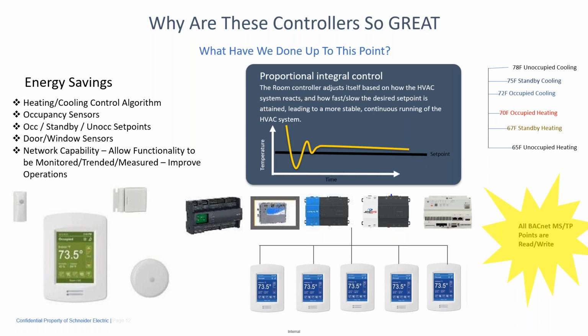points. So you've got the occupied set points, you've got the standby set points, but then you also have the unoccupied set points. If I don't sense motion for a longer period of time, I can go to my unoccupied set points and control to those. So energy savings is built in. You can also add door or window sensors, right? So either that can be hardwired to the controller, or you can use the wireless sensors. If the window is open, I'm going to turn off heat and cool and just let the fan run, right? If I close the window, everything is resumed. On the screen in that little spot in the bottom, when you have a window sensor connected to it, it says window open and turns off that heat and cool.